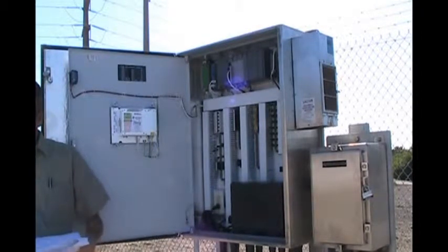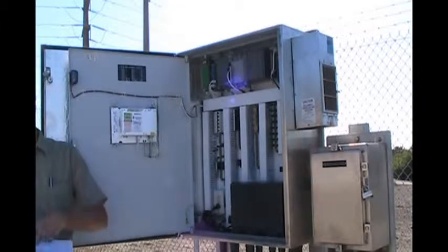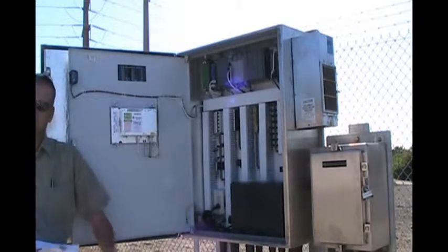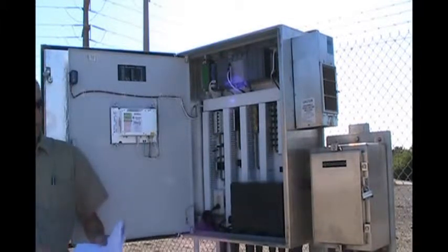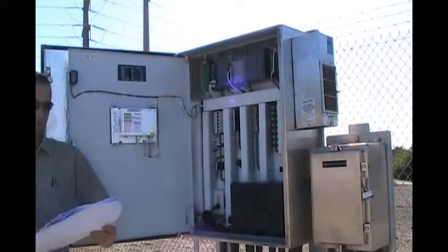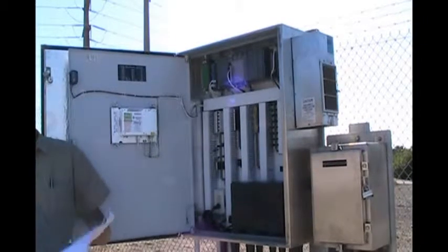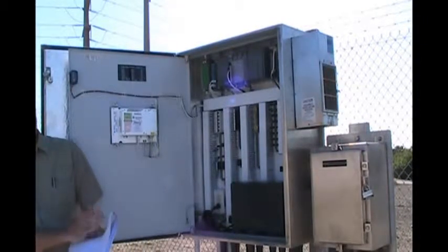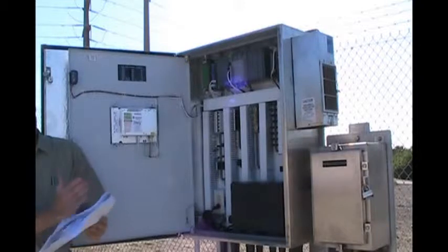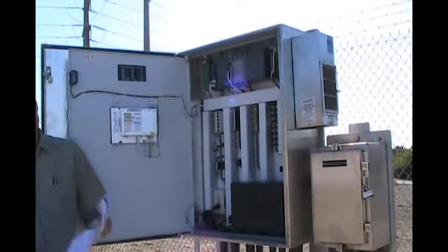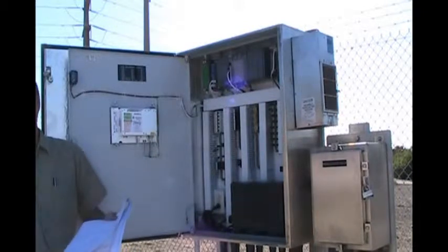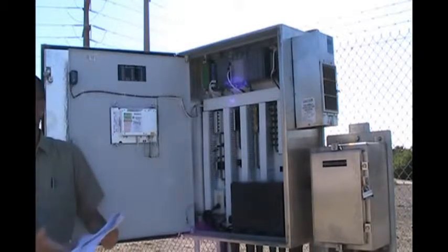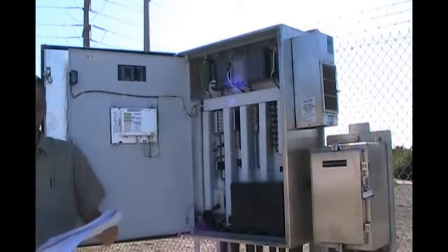Okay, so on the next section, we go from D section for power distribution to section E, which is the control part of the wiring. And the setup on each column is a card. So on the first card, the left-hand side, since these are all inputs, the field's on the left side, the card's on the right. The second column is outputs, so the card's on the left, the outputs are on the right. So you can just look at it and know it's an input or an output because of the direction the wires are headed.